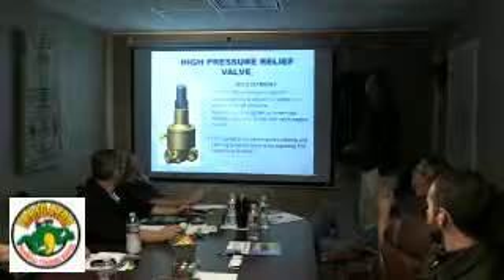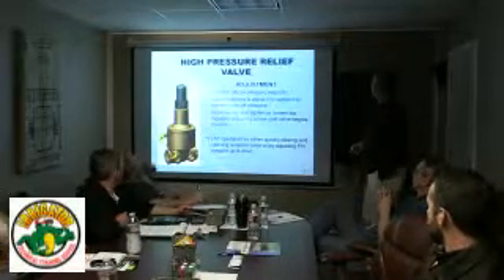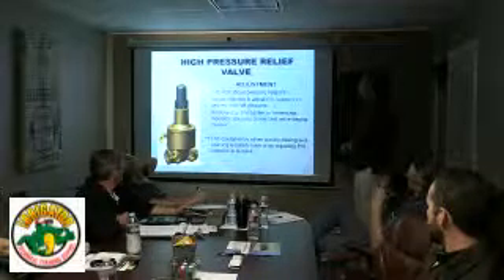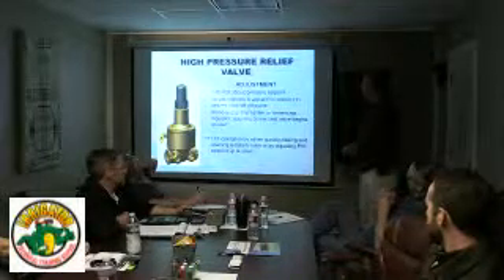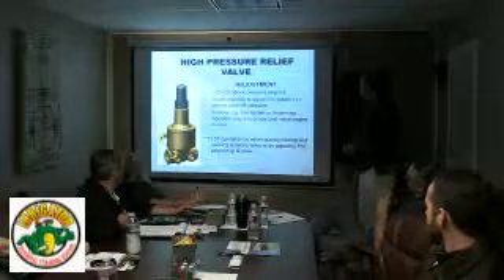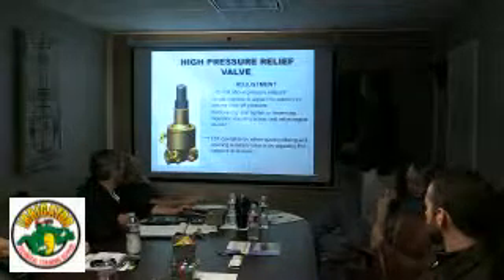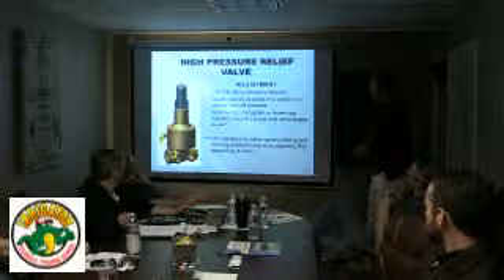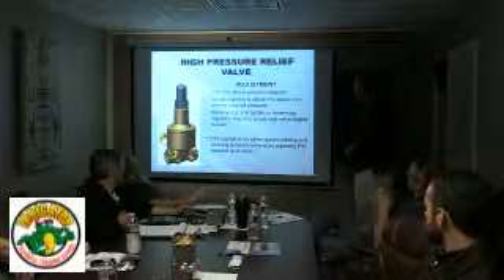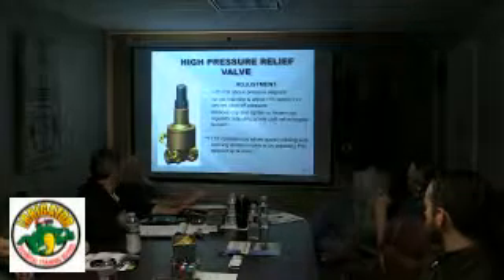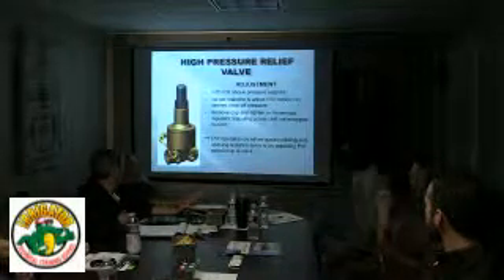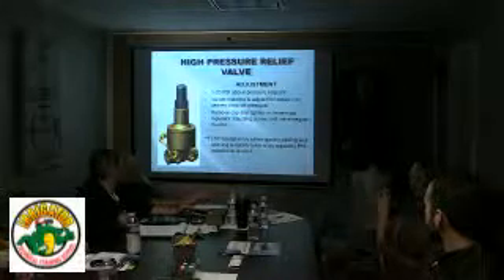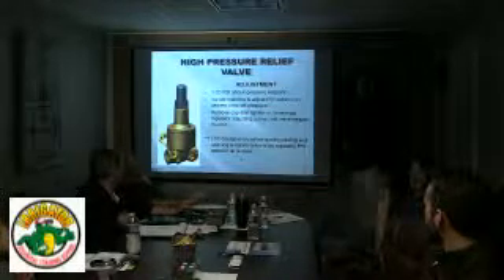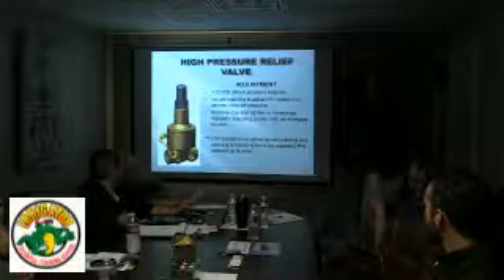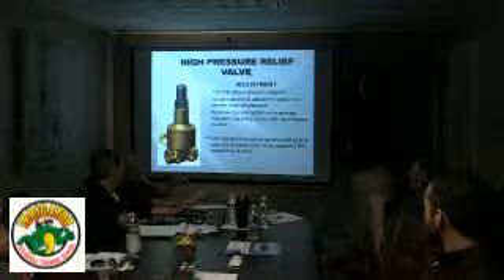Again, here's how you adjust it. We've got 5 to 20 PSI in here. It all depends on the system. It's usually 10 to 15 above your operating pressure. You can test these by opening and closing your discharge isolation valve. I like to close the valve and turn it into hand and then operate that speed potentiometer on the door and get it up to the pressure where you want it to open and make sure it's opening. Sometimes you can visually see the discharge, if it's down the wet well, you can open up the hatch and see when the valve opens and closes.